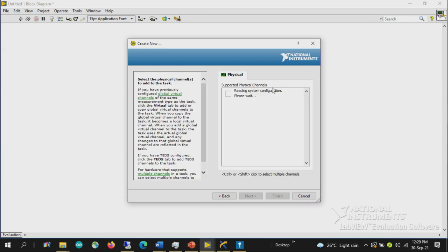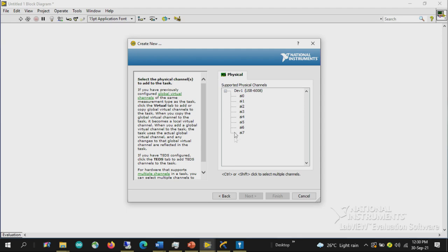I am selecting voltage. Based on the device connected, the available number of channels will be displayed. As discussed, our intention was to acquire differential data — this USB DAQ supports up to 4 channels for differential mode, or 8 channels for single-ended mode. Since we have not yet selected single-ended or differential, all 8 channels referenced to single-ended ground are shown. Since the sensor is connected with the second terminal internally grounded, we can take a single channel.